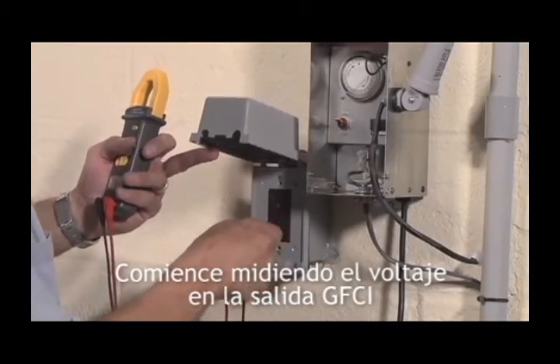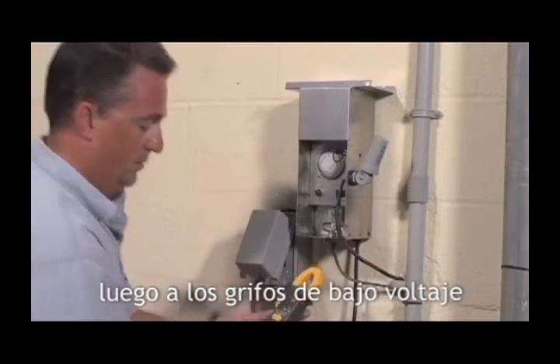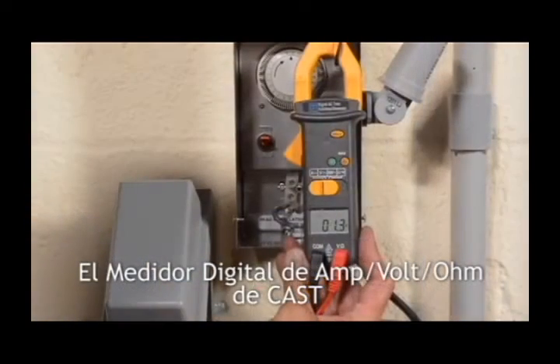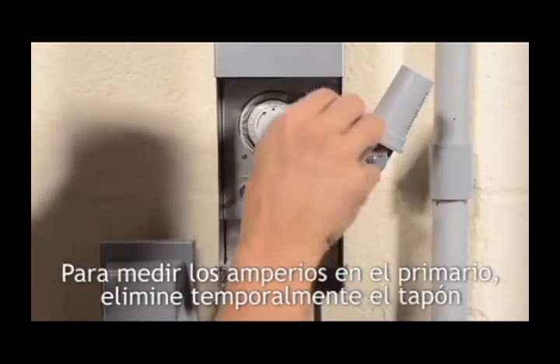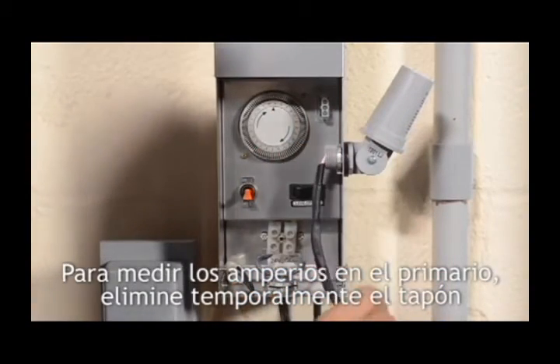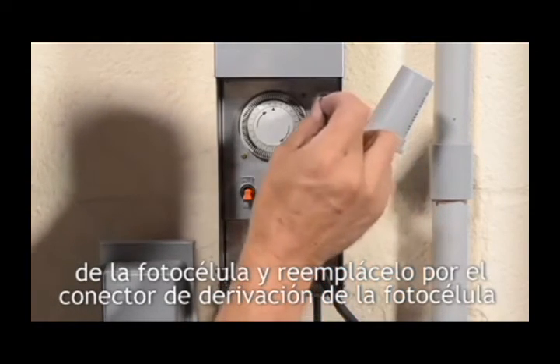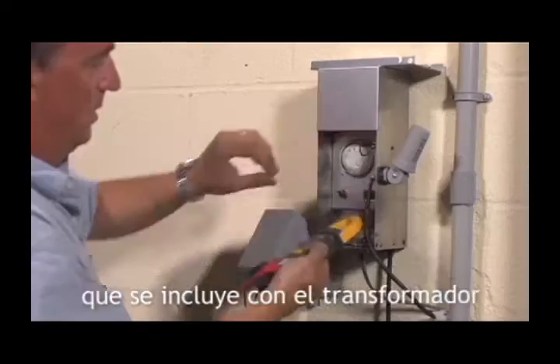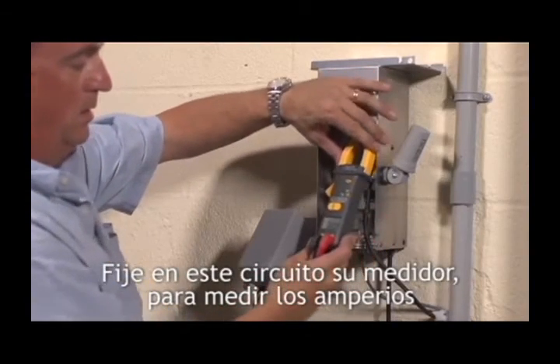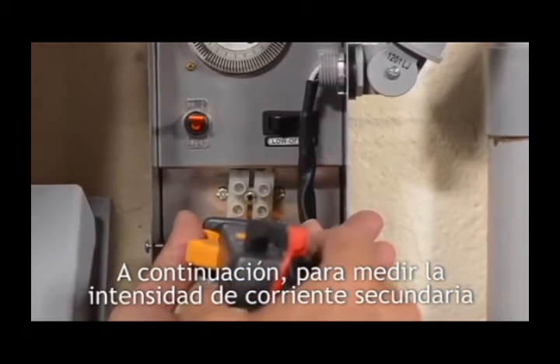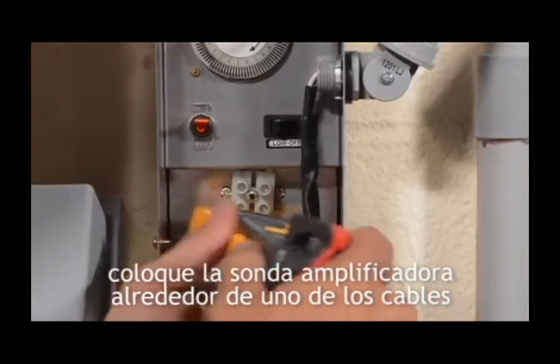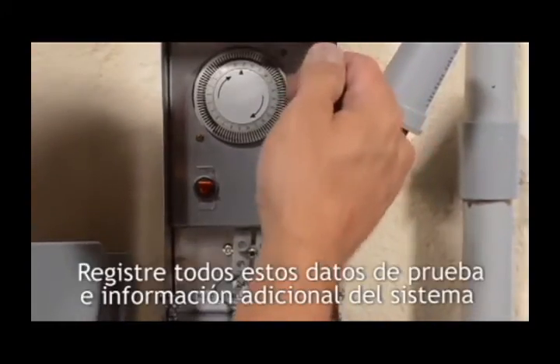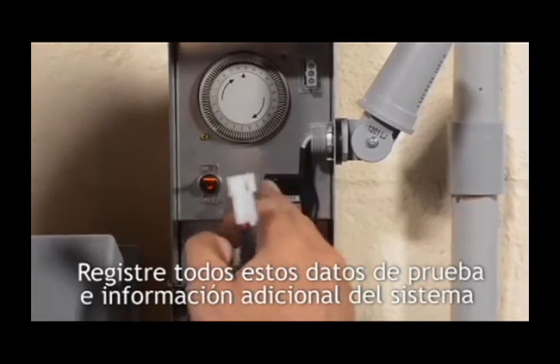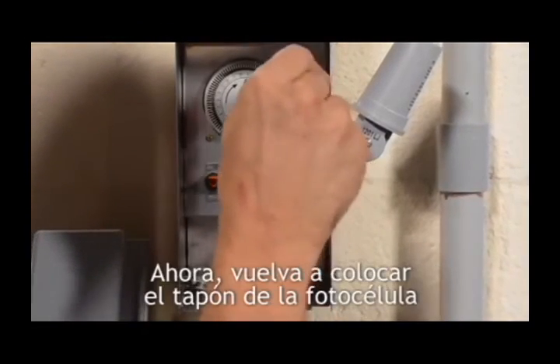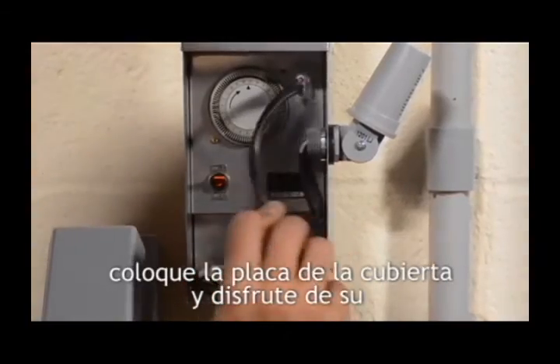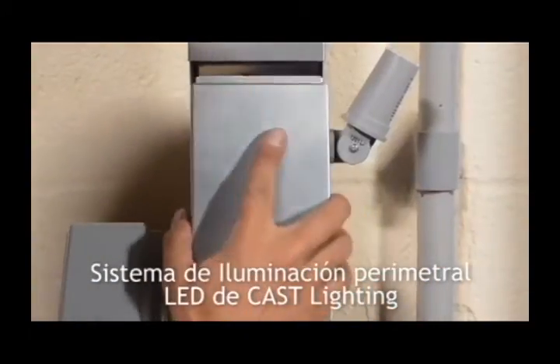Start by measuring voltage at the GFCI outlet. Then at the low voltage taps, the Cast Digital Amp Volt Ohms meter is a good tool for this job. To measure amps on the primary, temporarily remove the photocell plug and replace it with the photocell bypass plug that came with the transformer. Clamp onto this loop with your meter to measure the amps. Next, to measure the secondary amperage, place the amp probe around one of the wires attached to the low voltage tap. Record all the test data and other system information on the project record form. Now replace the photocell plug, attach the cover plate, and enjoy your Cast LED perimeter lighting system.